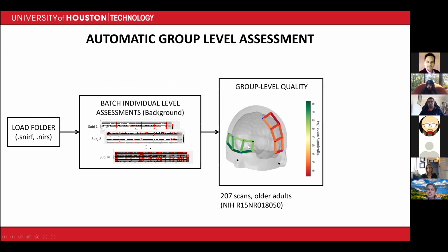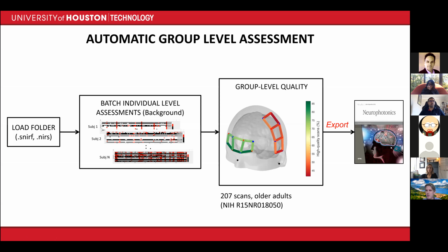And you can clearly see that the optical probe in the frontal area has excellent quality of the data. Below the hairline, it decreases only slightly, for optical channels above the hairline, but of course the lateral probe is a little bit more problematic because of hair obstruction. And this is something that investigators may want to maybe present in their publications for transparency, of course.